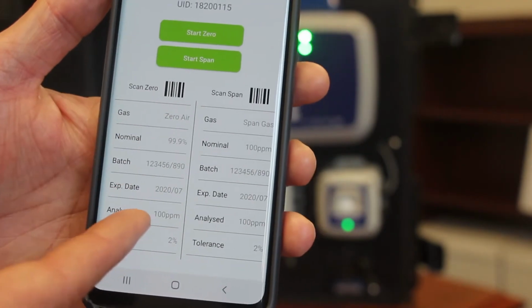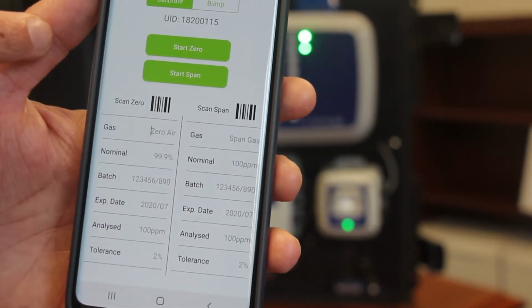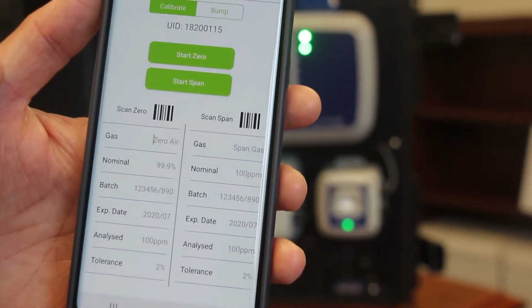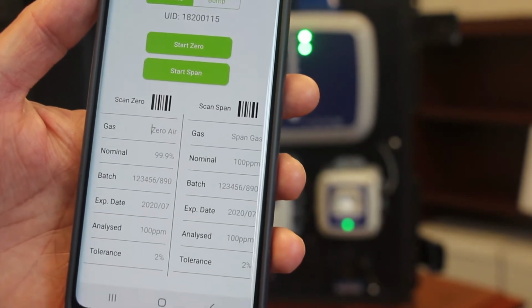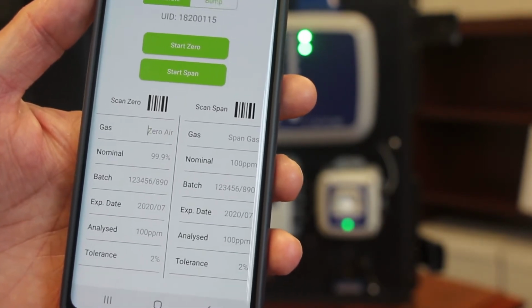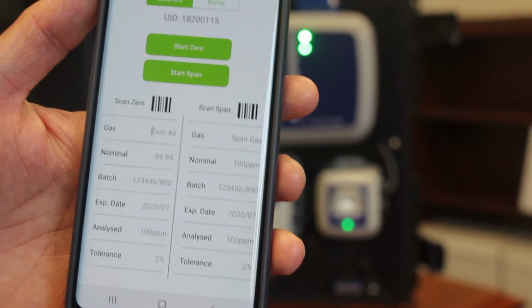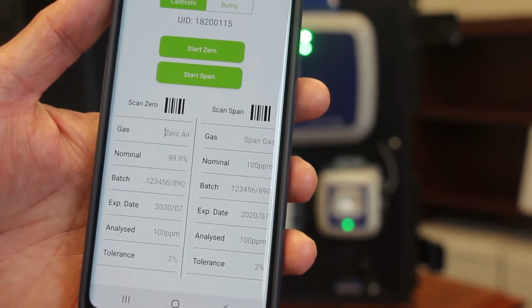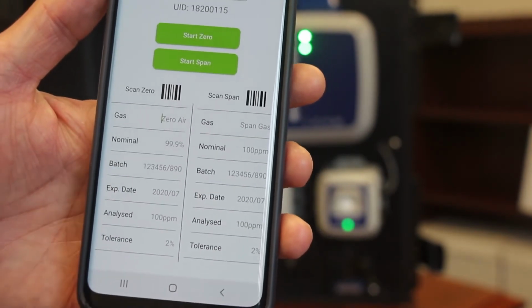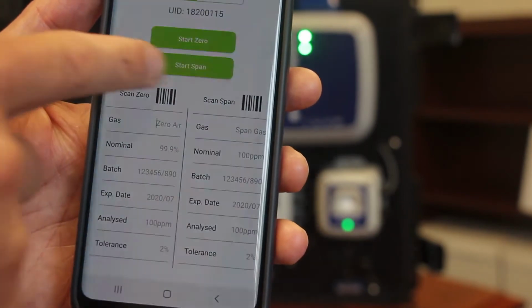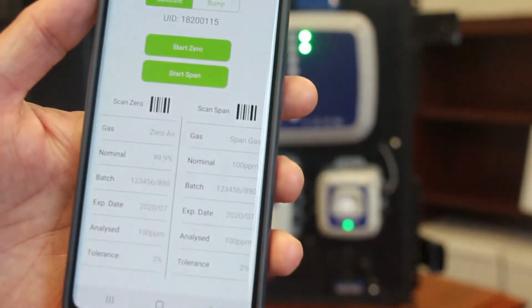So once you have your calibration gas details in here, you will simply click to start the zero calibration, and that will set a zero baseline of the sensor so that the sensor knows that there is actually 0 ppm of the target gas there. Once the zero calibration is complete, you will click and start the span calibration.